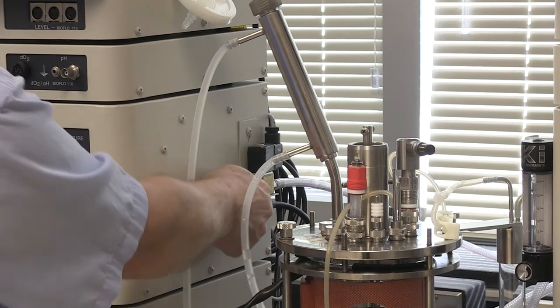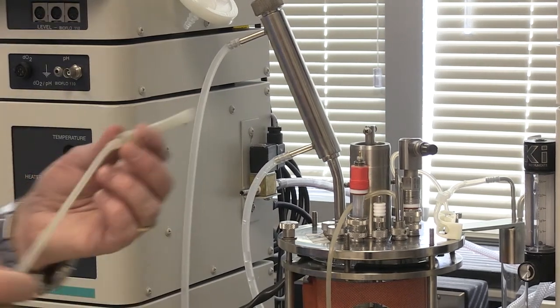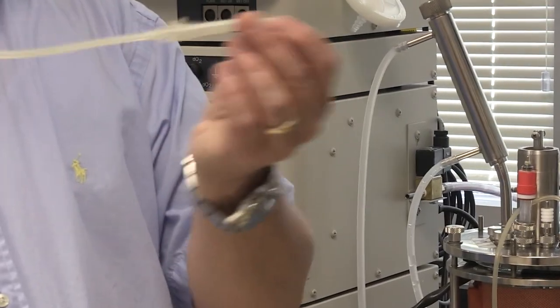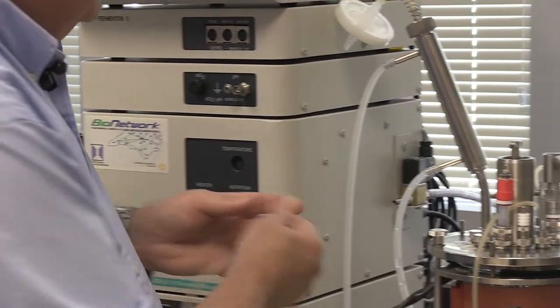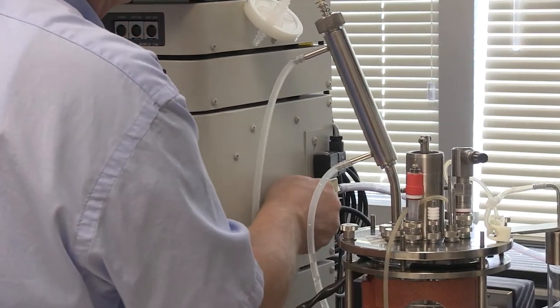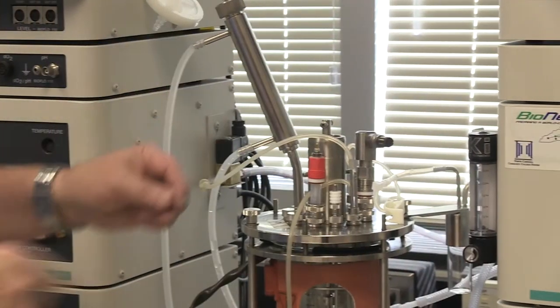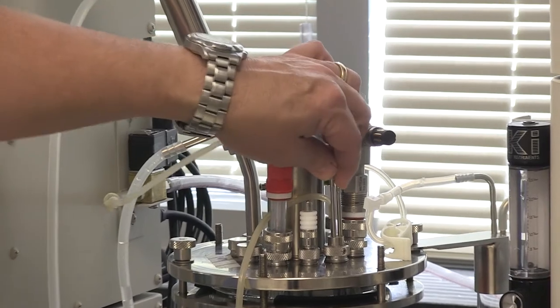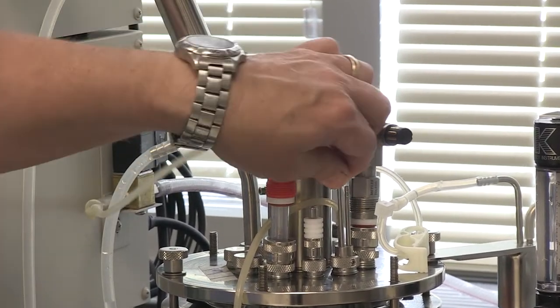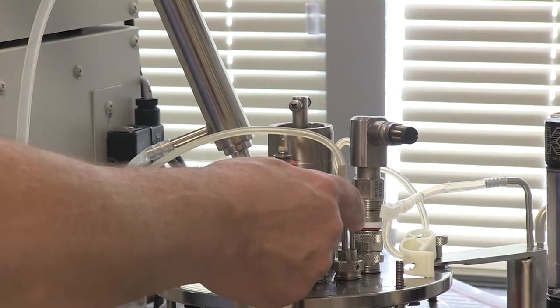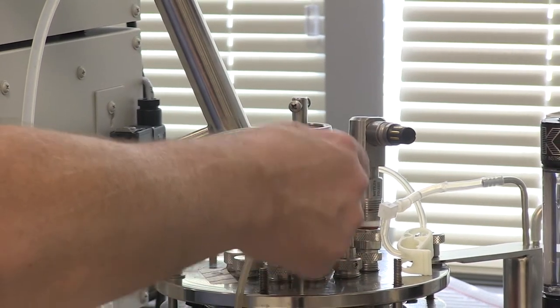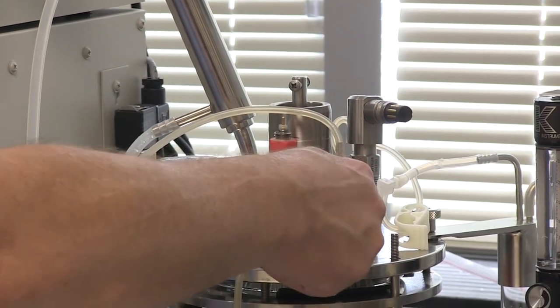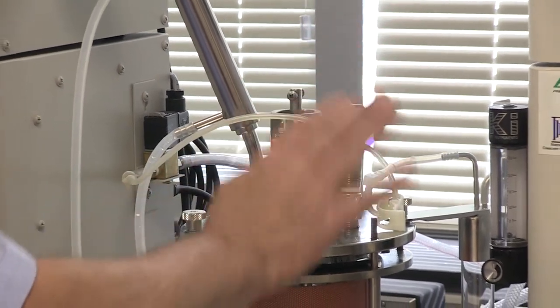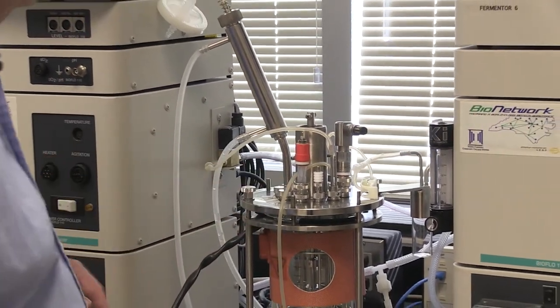Great. Now, to feed the cooling coil, we have to have one of those step-down tubings, because remember, the cooling coil is a small tubing, and the solenoid is large. So it goes from the solenoid to one side of the cooling coil. And since the cooling coil is a closed loop, it doesn't matter which side you make the in and which side you make the out. Now, before I'm finished, I'm going to have to get a small tubing to run to the drain or to the recirculating unit from this side. But for right now, I'm just going to leave that open while I hook up the other thing.